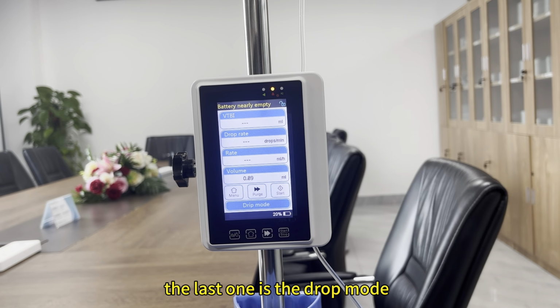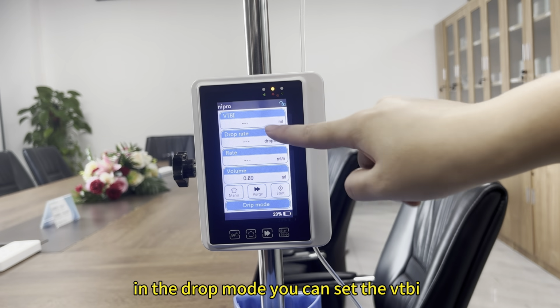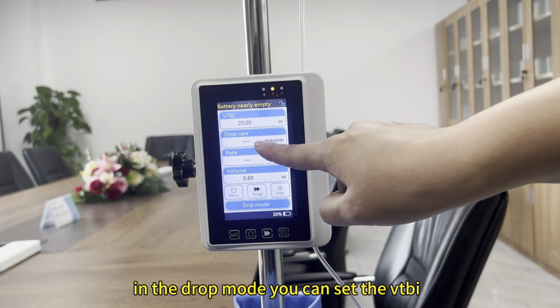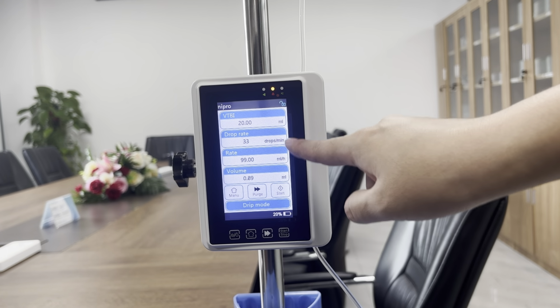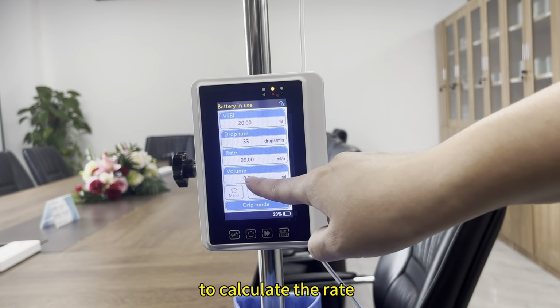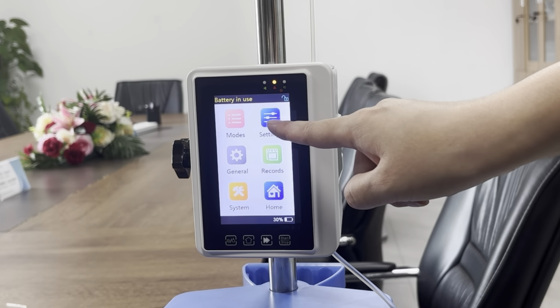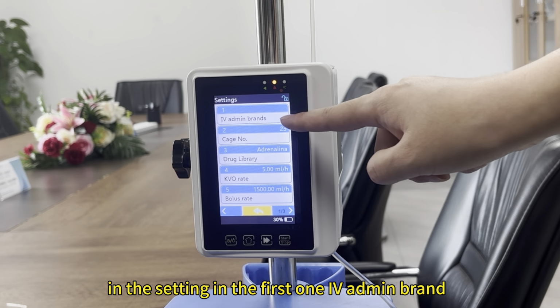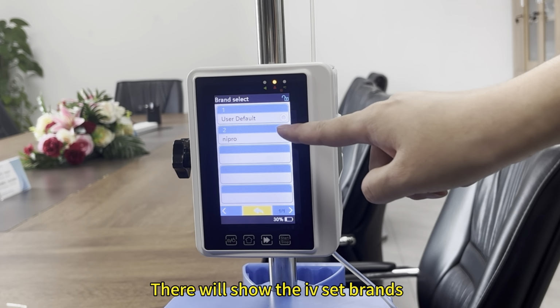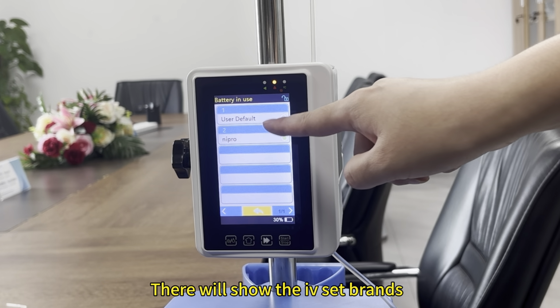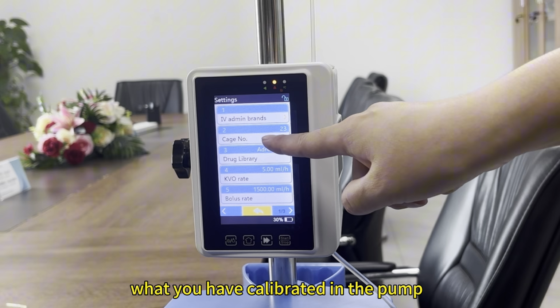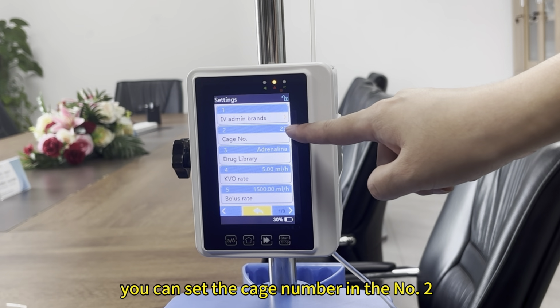The last one is the drip mode. In the drip mode, you can set the VTBI and set the drop rate. Then it will automatically calculate the infusion rate. In the setting, the first one, IV admin brand, it will show IV set brand that you have calibrated in the pump. You can set the cage number in number 2.